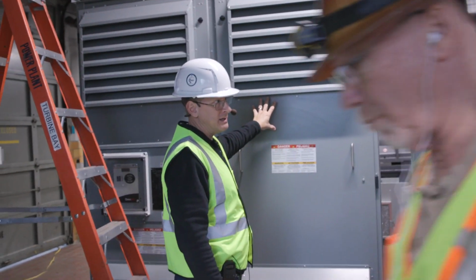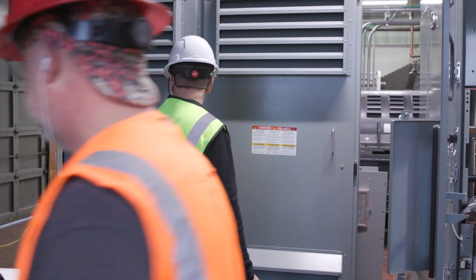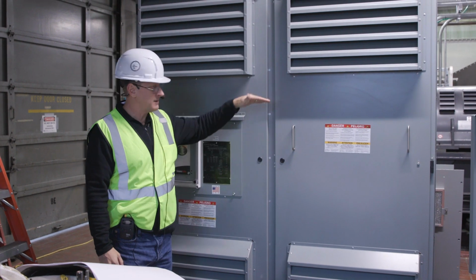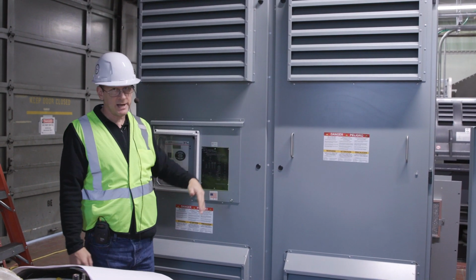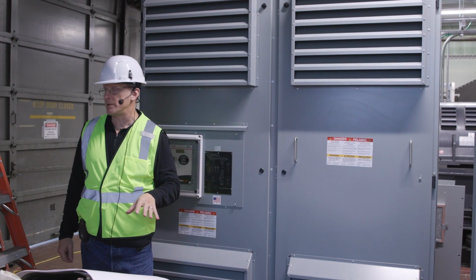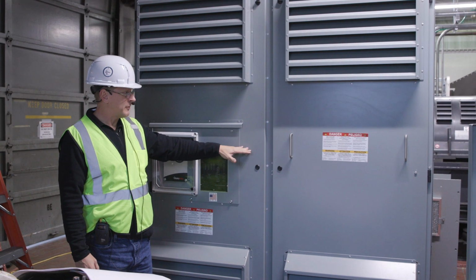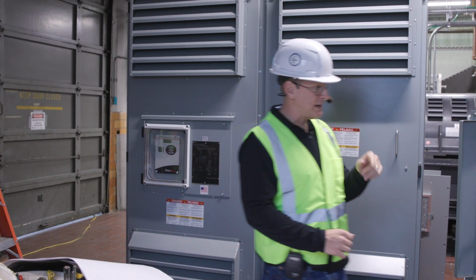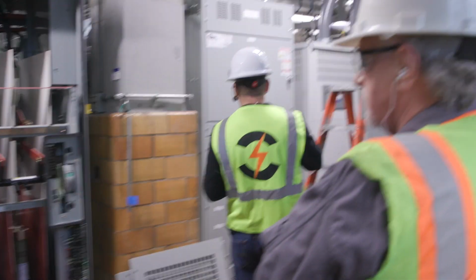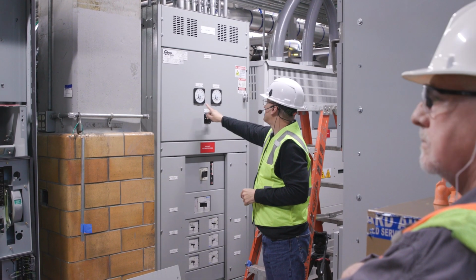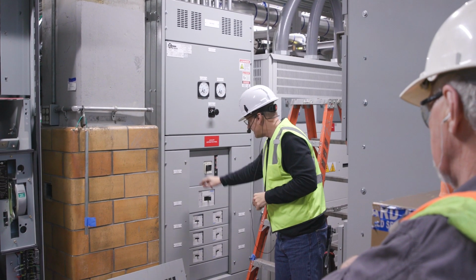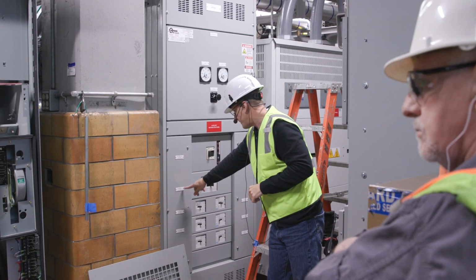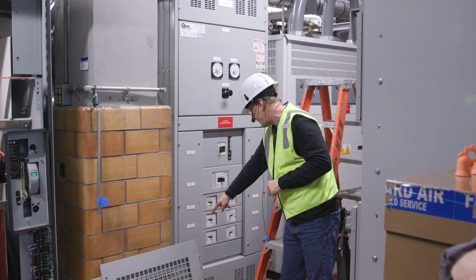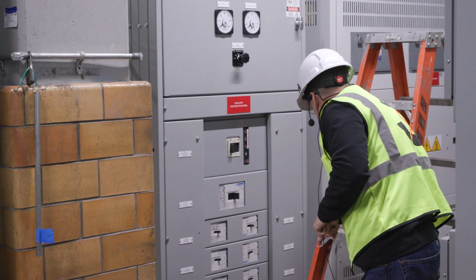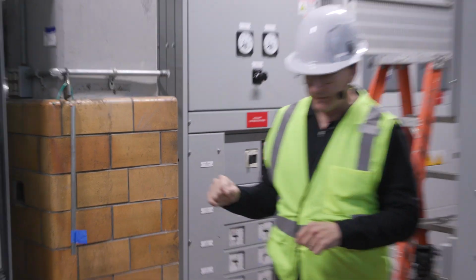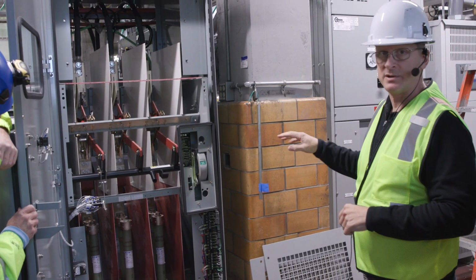So this is the GTP, generator transformer panel, fed by the Q20. So this takes your 4160 from the Q20 breaker, knocks it down to 480 volt three phase for all of our 480 volt auxiliaries. So the low voltage side, the 480, comes out of this transformer and goes into our ADP, which is right here. This is the ADP. So all of these feeds, and you can see they're labeled as far as what they feed. This one feeds the UPS, RCP, vent fan 1 and 2, spare, UCP supply. So from the transformer low voltage side into the ADP and then out to our various auxiliaries.